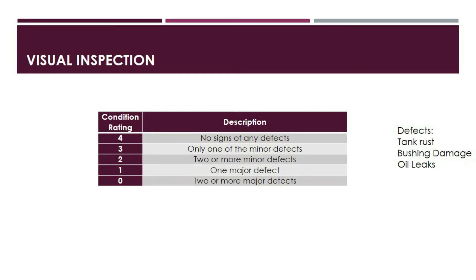The third category is the visual inspection. A rating of 4 means there is no rust on tank or enclosure, no damage to bushings, and no sign of oil leaks. A rating of 3 means minor occurrences of one defect, such as tank rust, bushing damage, or oil leaks. A rating of 2 means two or more defects are present but do not impact safe condition. A rating of 1 means the tank or radiator is badly rusted, there is major damage to bushings, or there is a major oil leak. A rating of 0 means two or more of these conditions are indicated as significant defects.